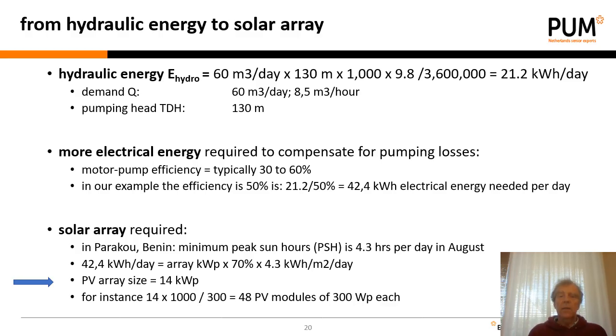And then if we look at the electrical energy that we require, we also have to add to this the losses that we have. We have a motor pump efficiency, and typically that's quite low, so that's 30 to 60%. Now, for this example, we assume that the efficiency is 50%. So instead of the 21.2 kilowatt hour per day, we need 42.4 kilowatt hours.